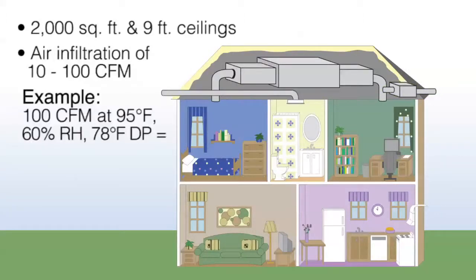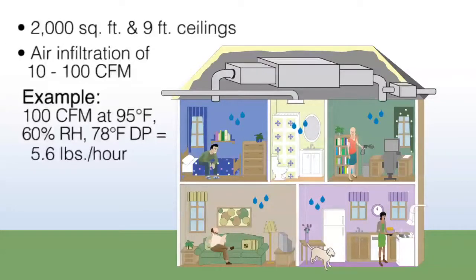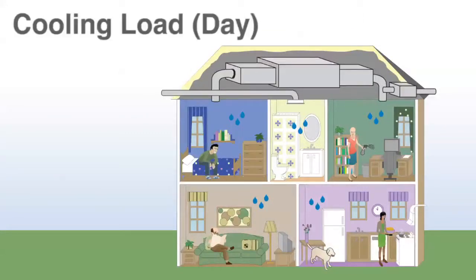With 100 CFM at 95 degrees and 60% RH — which is a 78 degree dew point — we've got about 5.6 pounds of water that enters the home above what we'd like. For people in a home, respiration and activity would add about 2 pounds per hour. So the total load of moisture on that home from occupants and infiltration is 7.6 pounds per hour. The numbers we're using for outside load are based on a design day from ASHRAE, which is the hottest days of the year. Three to four percent of the days would be at that level, and of course we go all the way down to not needing any cooling at all, which could occur anytime during the warmer three seasons.